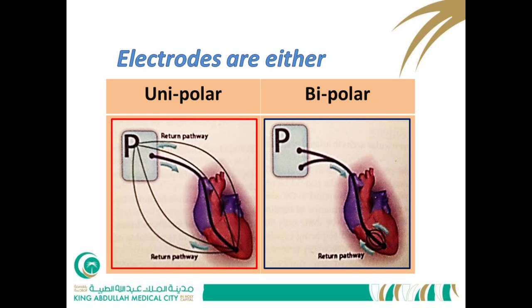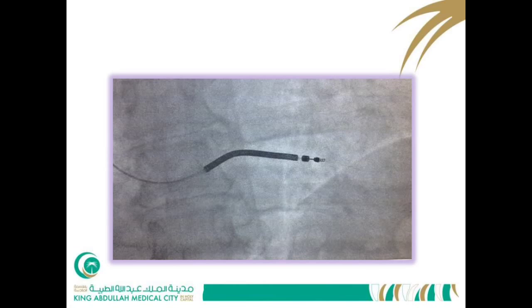Does this distinction make any difference? Yes, it does. The electrical field in a unipolar electrode is very large, whereas in a bipolar electrode it is limited to a small area. This makes electromagnetic interference much more common with unipolar leads than bipolar. The tip is the electrode; a bipolar lead has a nodule near the tip, and the thicker part of the lead is the shock coil.